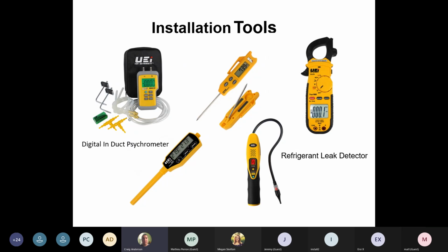Other tools that you should have in your truck: a refrigerant leak detector, if you're a service guy, probably a good thing to have if you've got that stubborn leak you can't find. A clamp-on meter to do your DC voltage, your AC voltage, your capacitor checks, a nice multimeter that does everything. A couple of pocket thermometers. Don't just buy one, buy two. We'll go through that later.